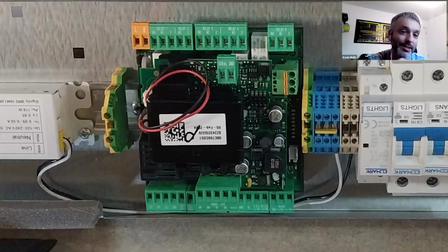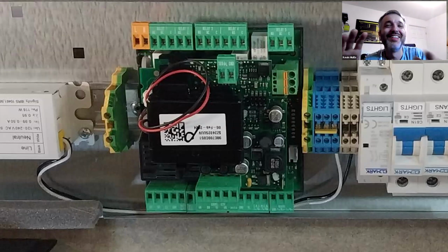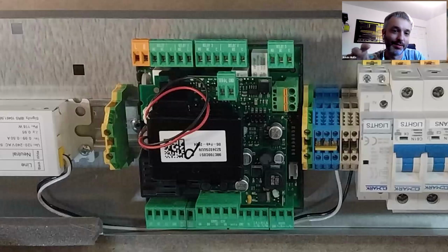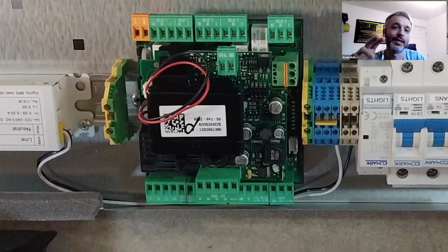Interestingly enough, if you ever need to do it, the baseboard of the MPX, they do an AKV version of the MXPro. You can actually use the baseboard of that controller for both. The module on top there with the battery in it unclips very carefully through a series of pins, and you can, if you're in a spot, take the AKV board off one and slot it onto that instead of the stepper board, and it'll work absolutely fine.